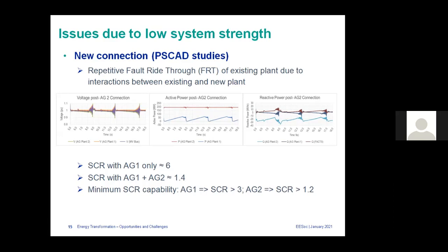Solar can do it, but with the wind, the problem is how to dump the energy. You need resistors. Solar can disconnect. Yeah, solar can still disconnect. But we don't want this to happen in the system because this is causing, you can see the voltage, this voltage is not acceptable because there's lots of flicker happening near 8 seconds and 9 seconds, fluctuations. So this is not good for the other customers, especially mines in the area. They say they have very voltage-sensitive loads, or mine motors, drives and like that, they trip. Then they complain when these things happen. And then you have to pay compensation and like that. So you can't really let this happen.